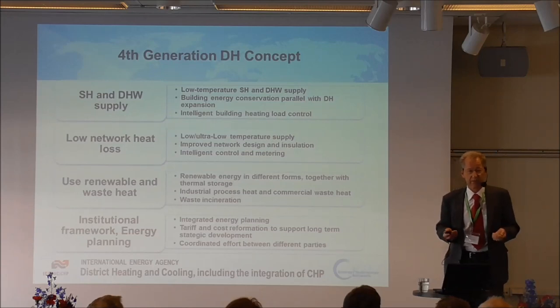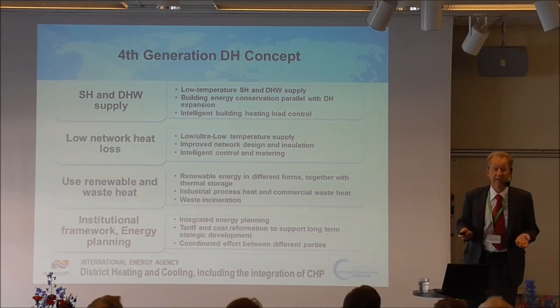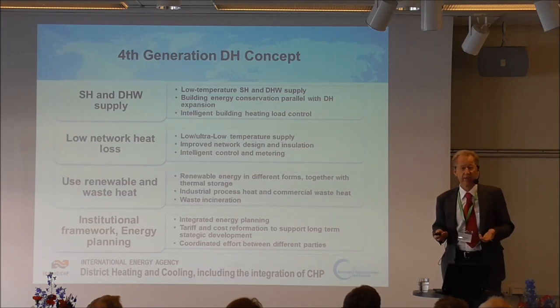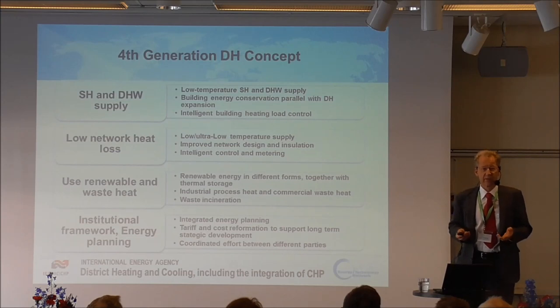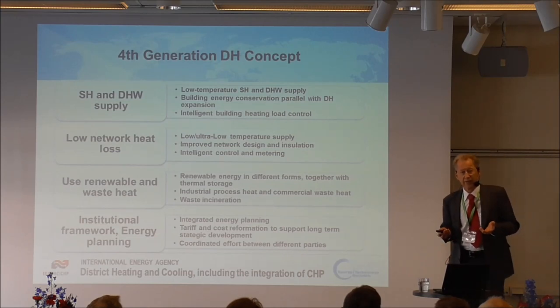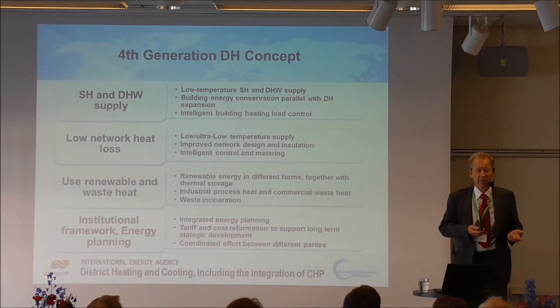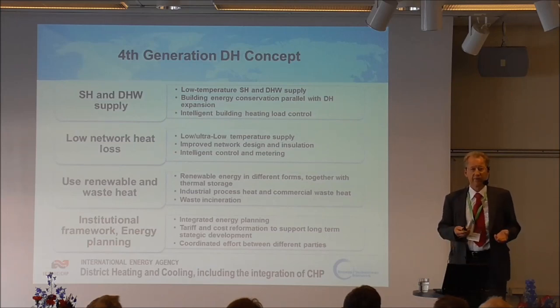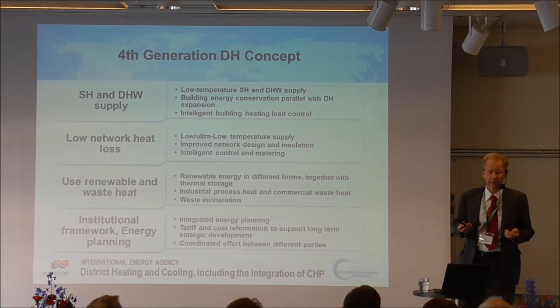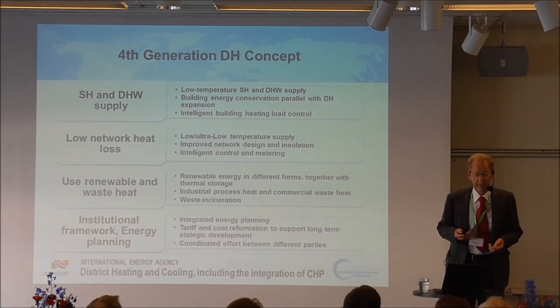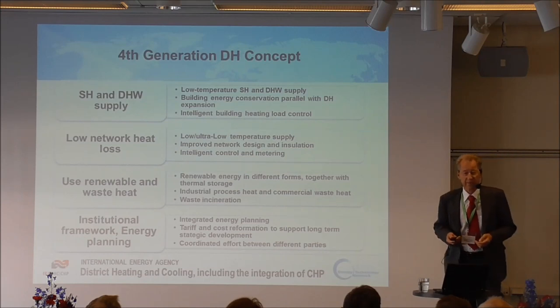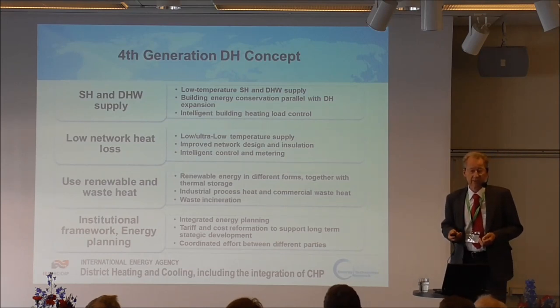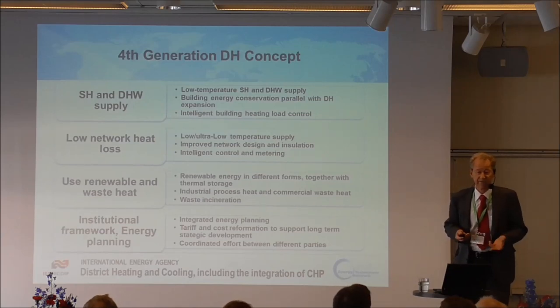The heat loss from the network mostly takes place over 8,000 hours a year, so if you have a little higher temperature for just a few hours in a year, that extra heat loss isn't important. So it's very nice to have this solution - you get the benefit without real risk, because if you have a lack of capacity you can always increase the network temperature, making the network safe. Many new possibilities can be used in designing low temperature, low heat loss, very efficient networks.